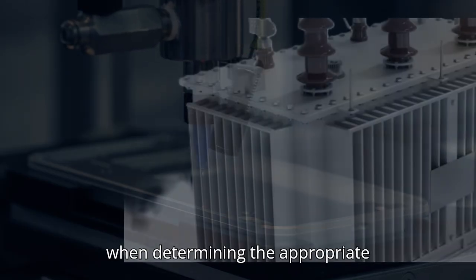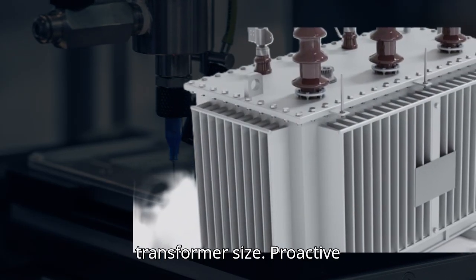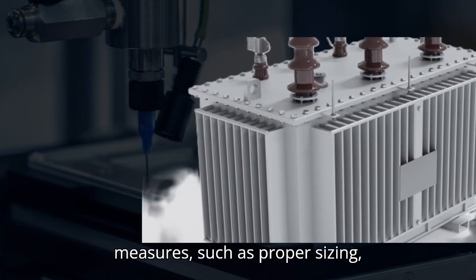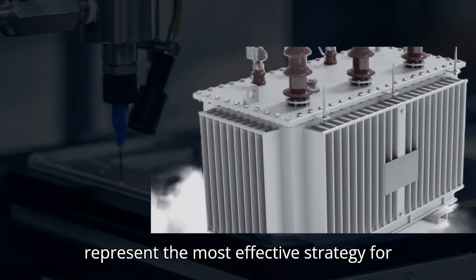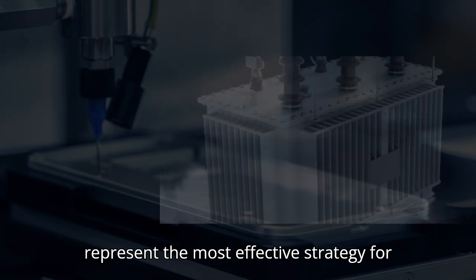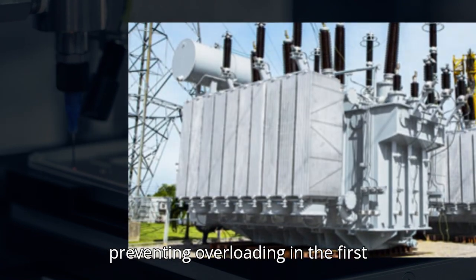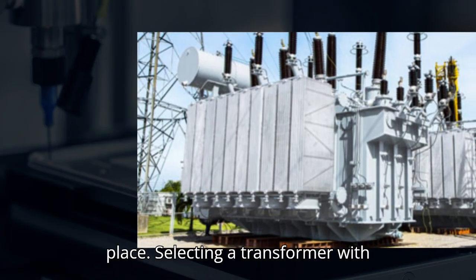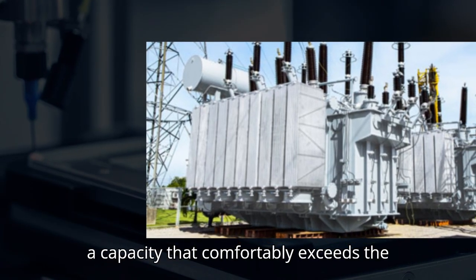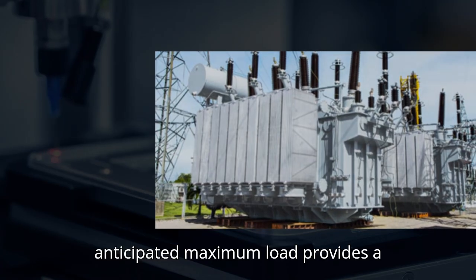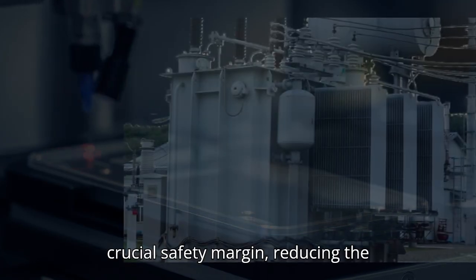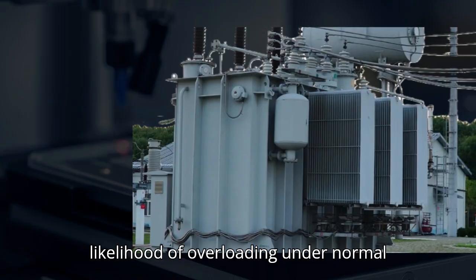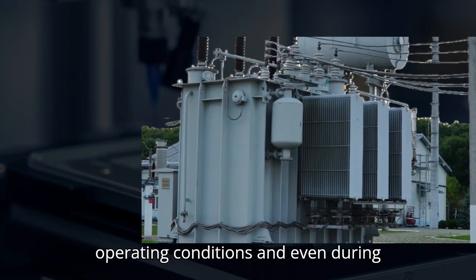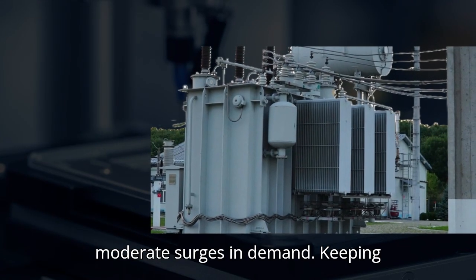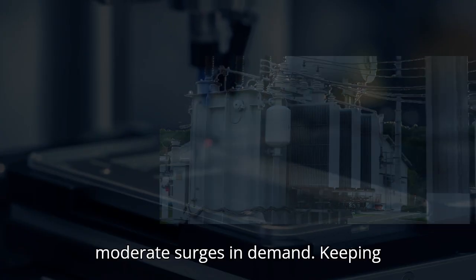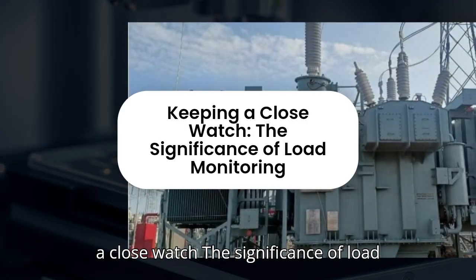It is also prudent to consider potential future load growth when determining the appropriate transformer size. Proactive measures such as proper sizing represent the most effective strategy for preventing overloading in the first place. Selecting a transformer with a capacity that comfortably exceeds the anticipated maximum load provides a crucial safety margin, reducing the likelihood of overloading under normal operating conditions and even during moderate surges in demand.